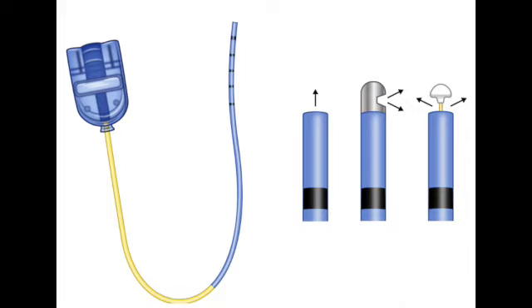This mode tackles a really practical problem. Imagine you're trying to treat tissue in the colon and the patient is breathing, or maybe they shift slightly. That means the distance between your catheter tip and the tissue is constantly changing, even by millimeters. Right, and you said the energy transfer depends on that distance. Hugely. So if the distance varies, the amount of energy actually hitting the tissue varies, leading to an uneven effect. Maybe too much in one spot, not enough in another. So precise APC fixes that.